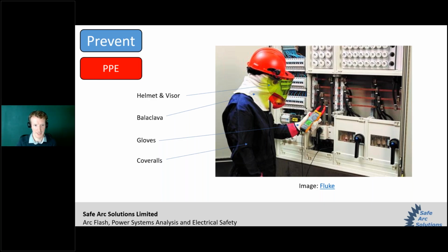There's a lot that could be said about Arc Flash PPE. Again, it's a whole webinar topic in and of itself, but really what you need to be looking for is that the Arc Flash PPE has a rating exceeding the incident energy that you've calculated as part of your Arc Flash study. You want more protection than the Arc can produce, to limit the possibility of injury. It's also worth bearing in mind that you don't want to be burdening workers with overly heavy or restrictive PPE, because this can make tasks more difficult or even unsafe, and it means that the PPE doesn't get worn out of frustration or inconvenience. So it's important to think about bringing the hazard down as much as you can as the first step, to get the incident energy down so that you're reducing the burden of what the PPE has to handle.